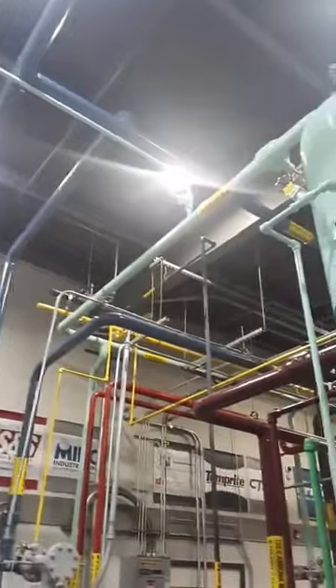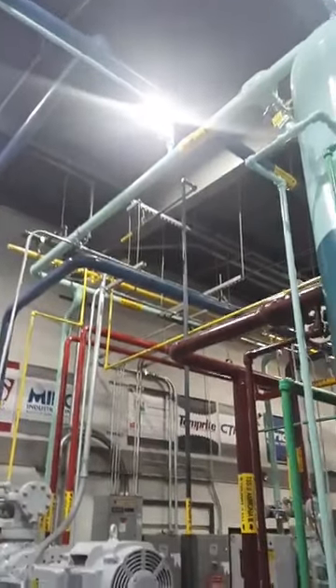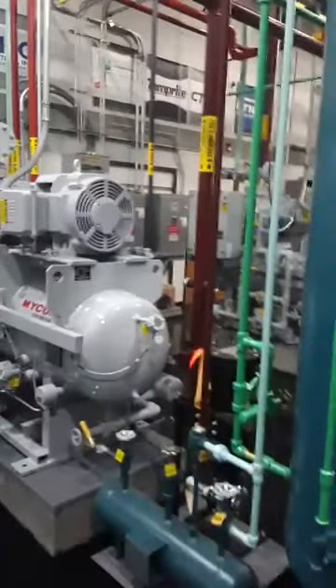But that ties to our saturated thermal siphon return line. With these systems, we've got to be real creative, because without a major heat load on them, even though some of the machinery we're using is maybe low capacity for heat transfer compared to some of these large industrial plants, we've got to create a load. So that turquoise line up there is what's going to give them a false load on the system, and we'll use the Danfoss motorized valve to bring that load from the high side to the low side.